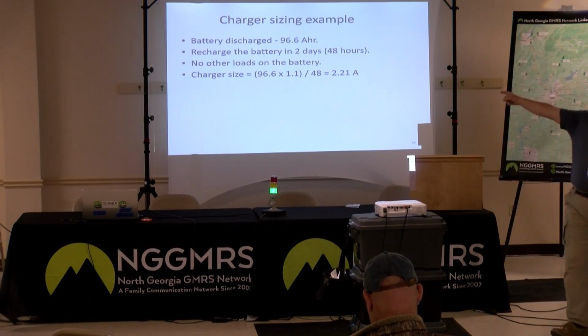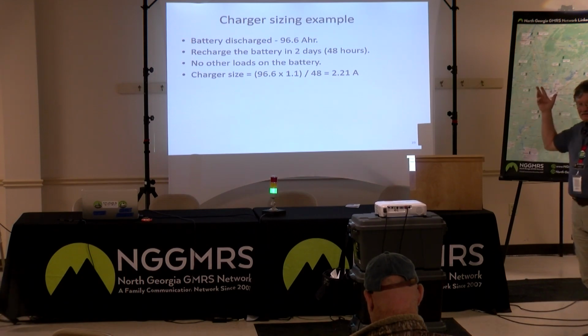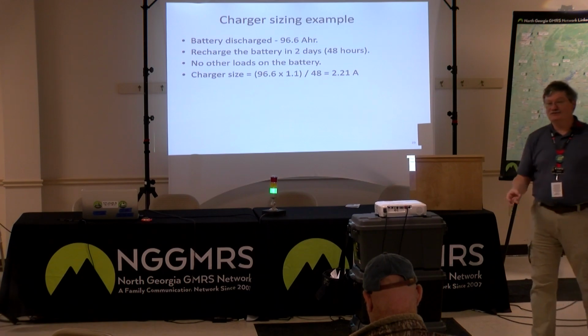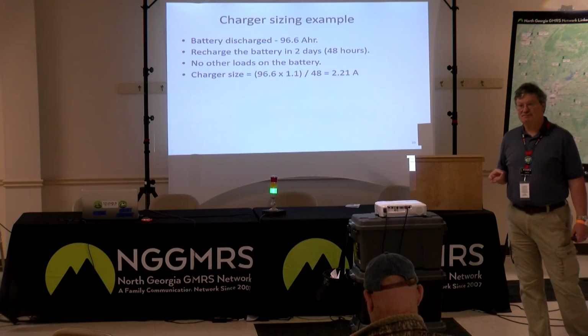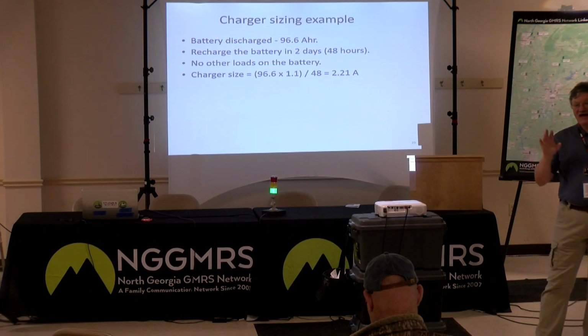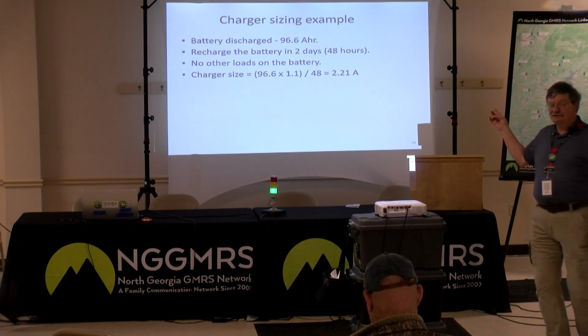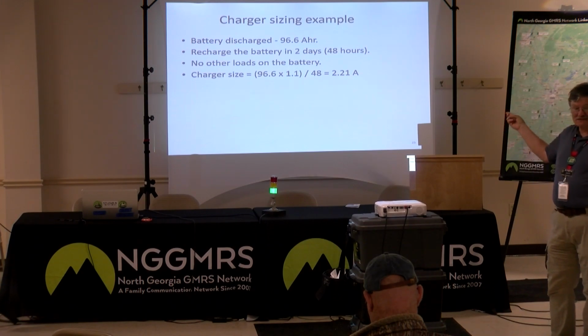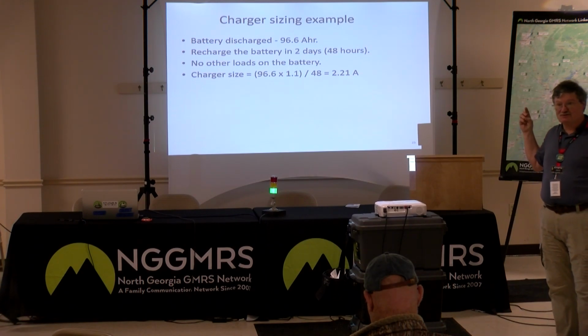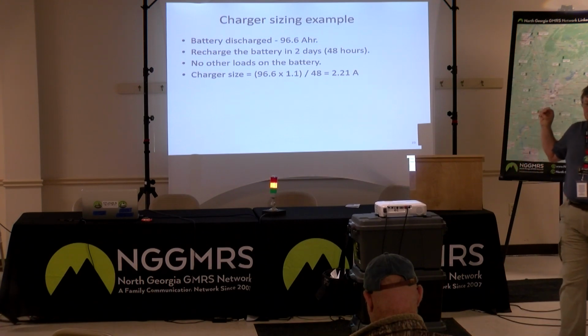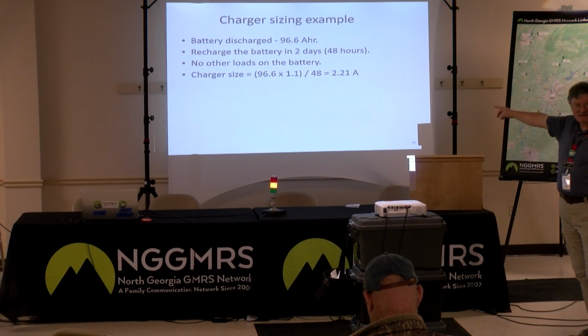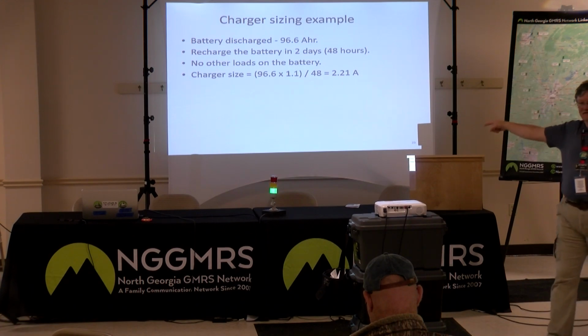What if I was operating the radio at this time? I was at 23 amps, I'd take the 2.21 and add 23 amps to it, which would put me at 25.21 amps. That would power my radio and transmit at full power, plus be recharging my battery. What I haven't allowed for is, when I'm off key, like that 22-hour bit, 2 hours on, 22 off, roughly 10% duty cycle, when I'm not transmitting, all 25 amps is available for the battery.